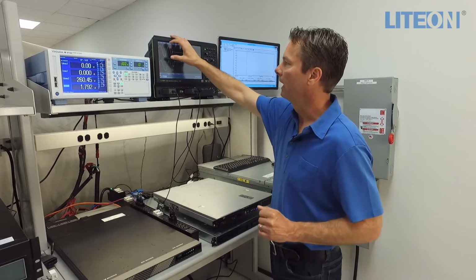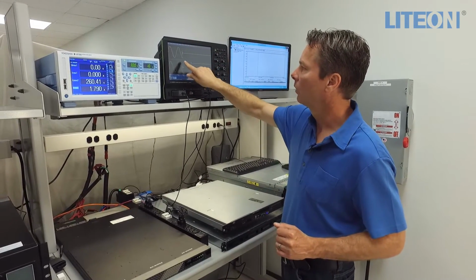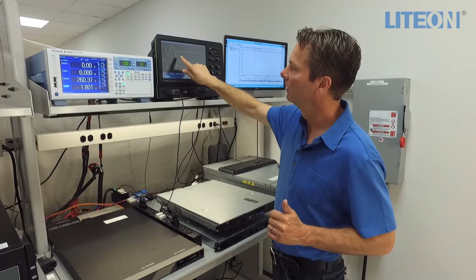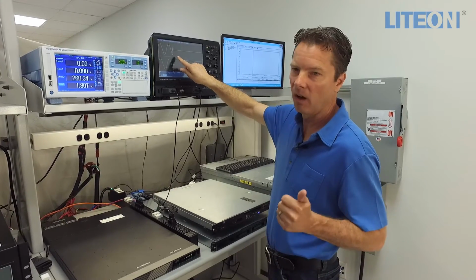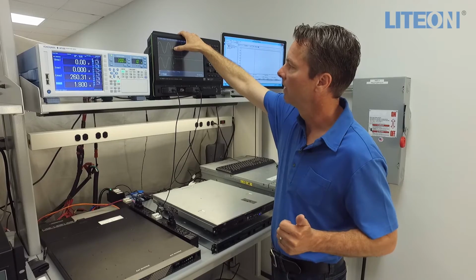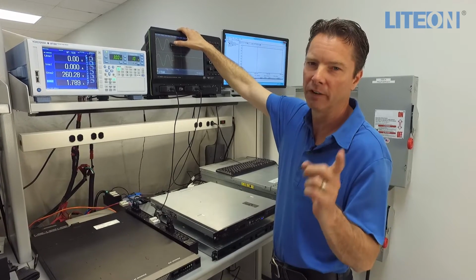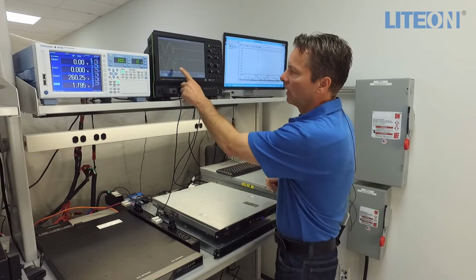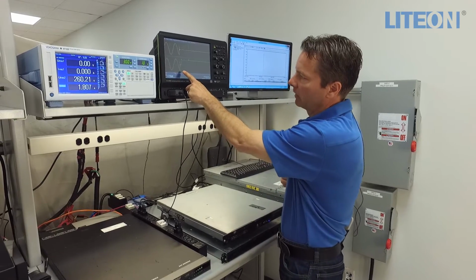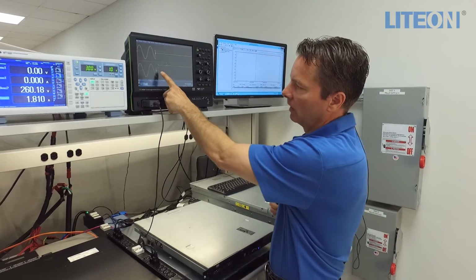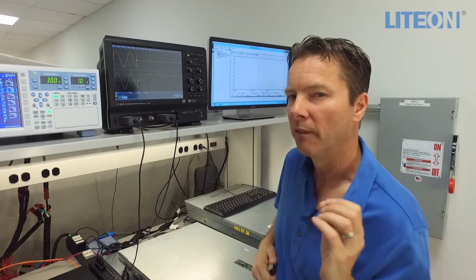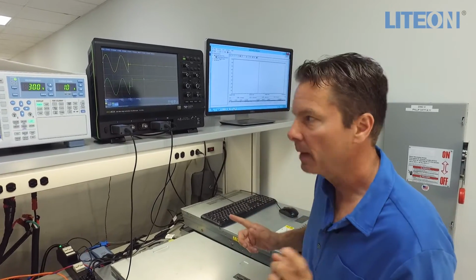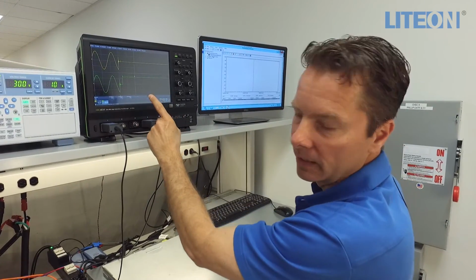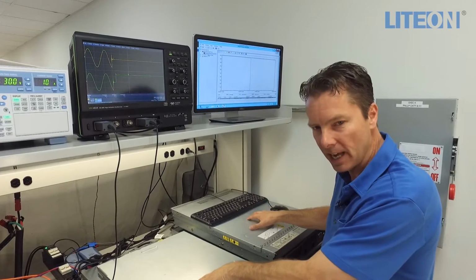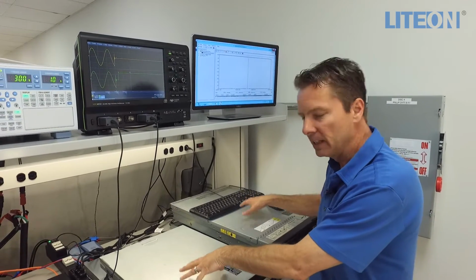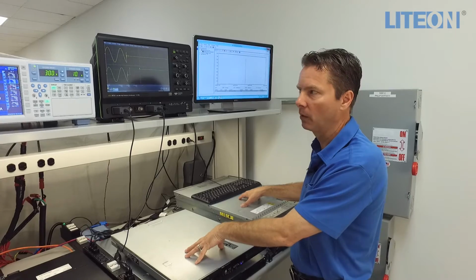Looking at my oscilloscope, right at about peak power during the cycle I lost power completely, and went to 0 voltage for a very, very short time. On the output of VPOC you can see again where I lost power, going to 0 voltage for a very short time—under 4 milliseconds, a time undetectable by this IT equipment. This IT equipment never saw a power outage.